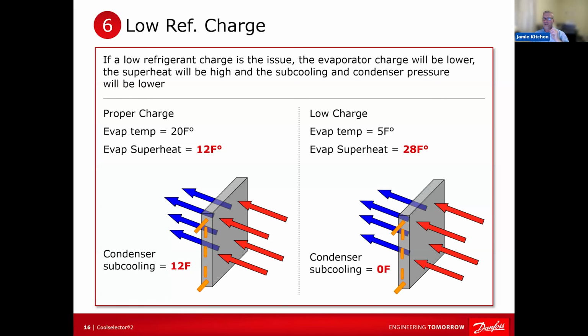So if your subcooling on your condenser is like 0 or 1 degree or 2 degrees or something, you're low on charge. And so the expectation is you don't have enough subcooling to maintain a column of liquid in your liquid line. How do you expect your TXV to work with that tiny little opening and you're trying to shove vapor through it, right? Not going to work. And so it'll also be unstable a lot of times. You'll see it going up and down. You see this a lot of times when people are charging AC systems and they don't put enough refrigerant charge in, you'll see it hunt.